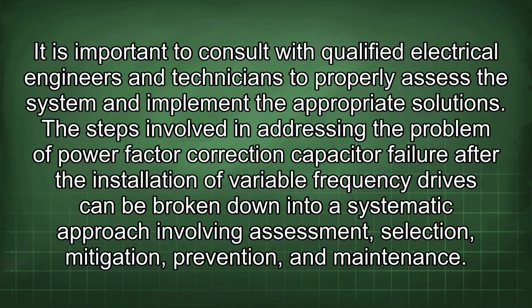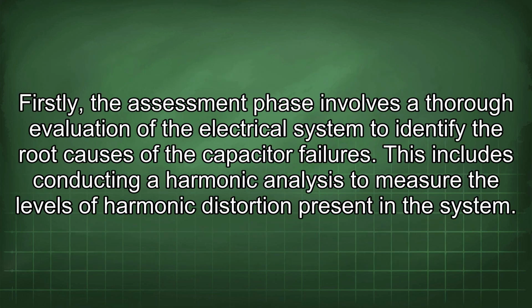The steps involved in addressing the problem of power factor correction capacitor failure after the installation of variable frequency drives can be broken down into a systematic approach involving assessment, selection, mitigation, prevention, and maintenance.